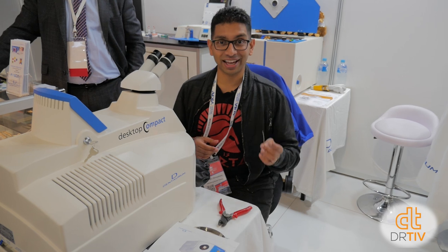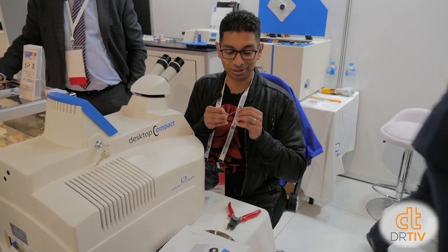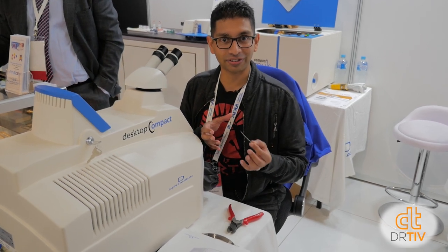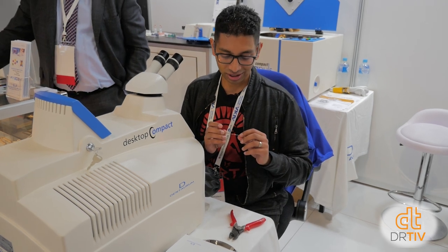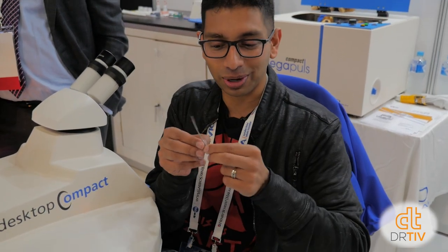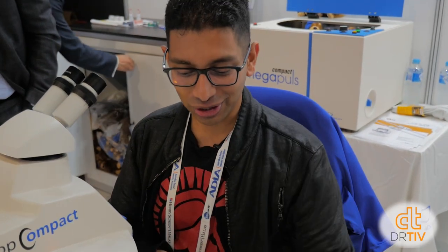I'm sitting in front of a desktop laser welder — this is from Dentaurum and it's called the Desktop Compact. This thing is $27,995. You can weld bits of metal together, which is pretty cool. It's not for adding brackets onto bands — that's your spot welder — but this is for putting broken clasps back onto dentures and things like that. First time I've ever laser welded something, it's really easy. I welded two bits of wire together and I can't break them apart. Pretty impressive.